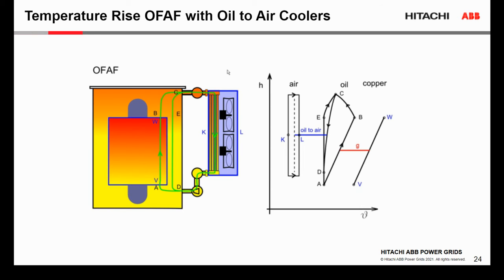And then it is a similar solution to the one before, but instead of radiators, we install the oil-to-air coolers. And with this solution, the transformer overall dimensions and also the amount of oil are reduced. But we may significantly increase the auxiliary losses due to the power needed by the coolers, and this solution also affects the maintenance.